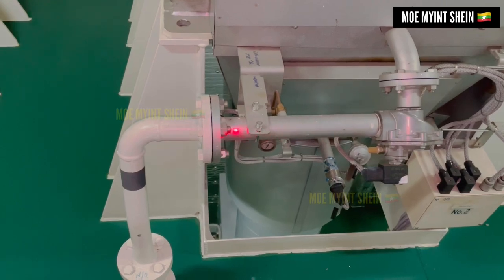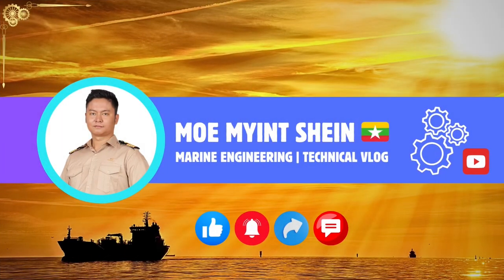The main concept of the SCR system is: when urea water is injected into high-temperature exhaust gas, ammonia is formed by thermal decomposition and hydrolysis. The formed ammonia and NOx are then reduced into harmless water and nitrogen through chemical reactions in the catalyst. Thanks for watching everyone — I appreciate your support. If you like this video, please consider subscribing, and I can't wait to see you in the next one.